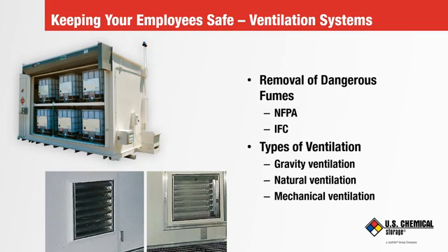Now we'll talk mechanical ventilation. It starts again with a low-level vent becoming the air intake, and the second low-level vent on the opposite wall acts as an output, similar to the gravity ventilation solution we already talked about. Here, outside the second vent, is installed a vertical stack or duct up the exterior wall. The fan, per NFPA 30 paragraph 18.5.5, shall provide 1 cubic foot per minute of exhaust air for each square foot of floor area, creating a negative pressure in the room. This comes to over 6 air changes per hour.